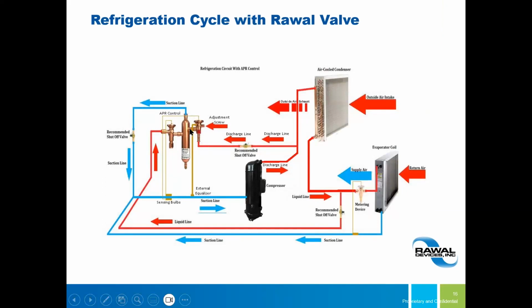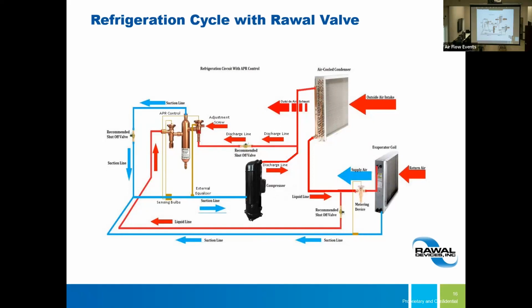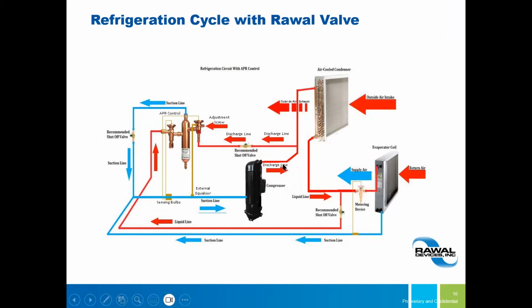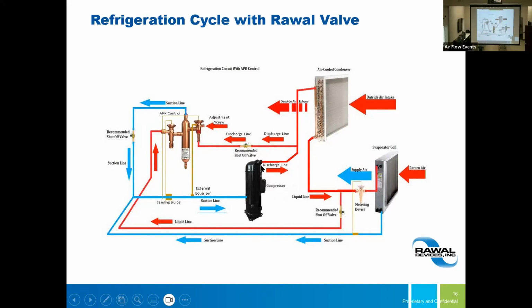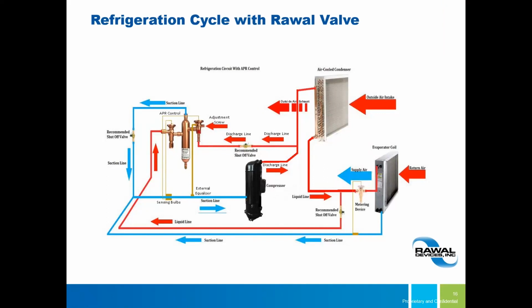So from there, you've got the discharge. Hold on here. Am I looking at it reversed? Now I'm all confused because it says discharge line into the... It's your hot gas off the compressor. Yeah, there it is. So yeah, that's right. I think the discharge line is the hot gas off the compressor. That's correct. Okay. And you're basically mixing the liquid and the gas in that chamber. That's correct.